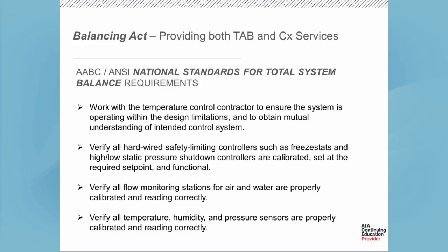In the AABC national standards, it's very, very clear about what the testing and balancing firm should provide with respect to controls verification. And it's working with the BAS contractor to ensure the system is operating within the design limitations and obtain mutual understanding of the intended control system. That can happen a little bit before, but are we getting the design intent out of the control system? Secondly, verifying all hardwired safety controllers such as freezestats and high-low static pressure shutdown controllers are calibrated. You can say this is a control provider or control contractor's function. In our experience, they typically install it and test the point, but they do not test the settings. And so we argue that the test and balance firm is the one that really needs to check those settings and ensure they're set up at the correct set point and they're functional.